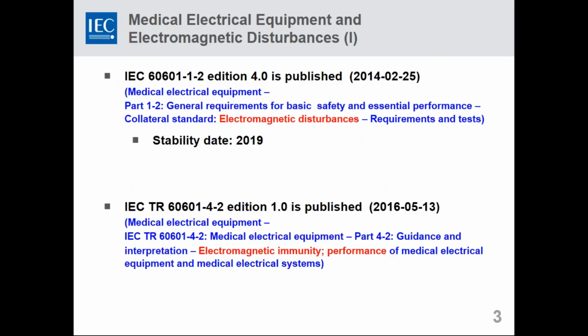Some of you may be familiar with the original EMC document that was a collateral to the safety document 60601-1-2 back in 2014 when it was published, and had a section, Annex J, on electromagnetic disturbances, which is the EMC part of it. Well, that part has been divorced and put into a new technical report, TR 60601-4-2, that was published in May of this year. And now all the electromagnetic immunity and performance material is there, and not in 60601-1-2. So if you do that medical device testing, you really need this technical report 4-2.